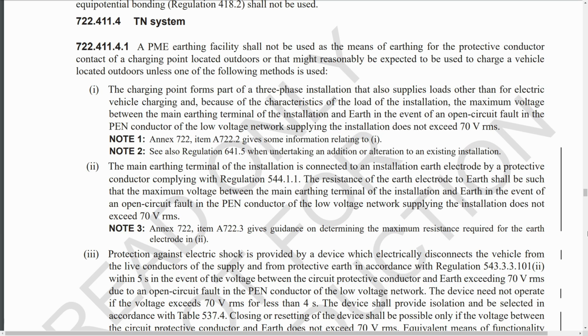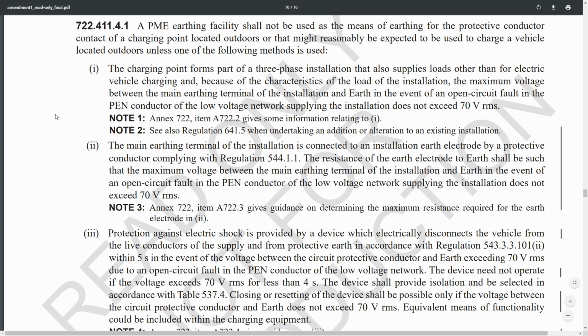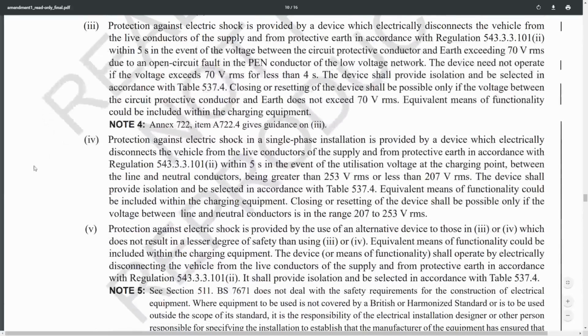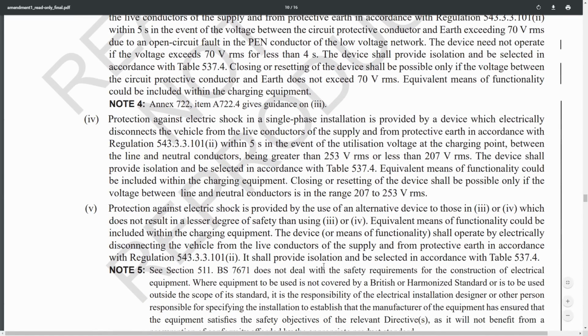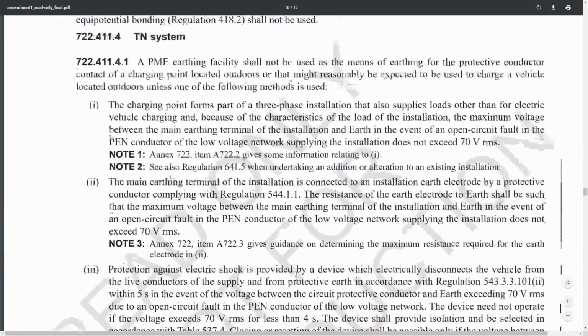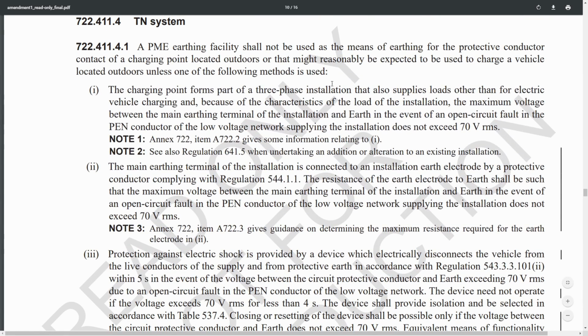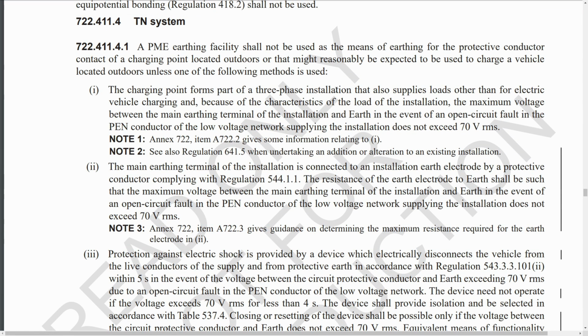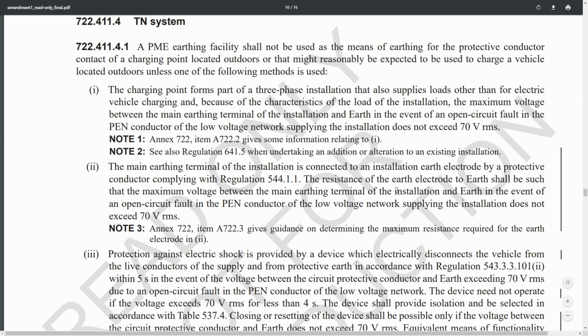The change here is that some of the text has been rewritten, and rather than having 3 items, we now actually have 5, so a couple of new items have been put in there as well. So this only applies to TN-C-S or PME type facilities, not applicable to TT or TN-S type installations. And your choices here are not to use the PME earthing facility. The only choice there is to convert it to a TT installation. And if you are going to use that PME earthing facility, it has to comply with one of these 5 items. So the first one is actually the same.